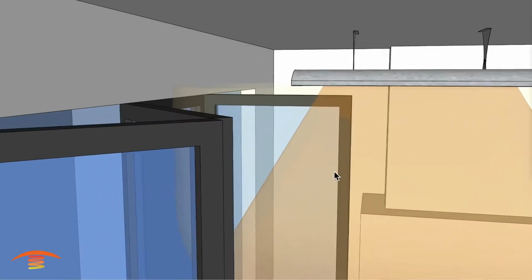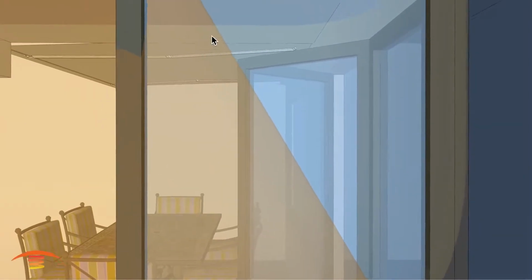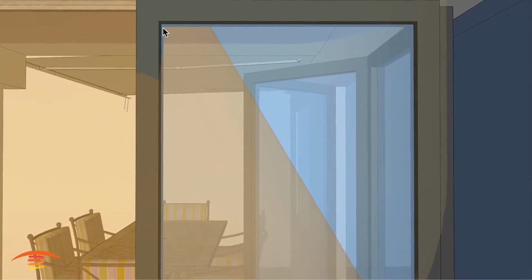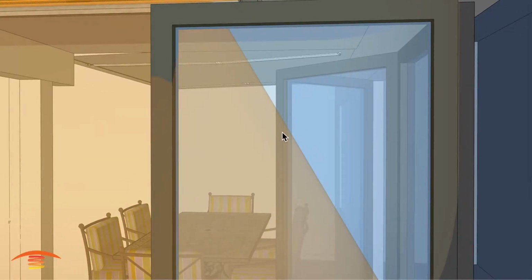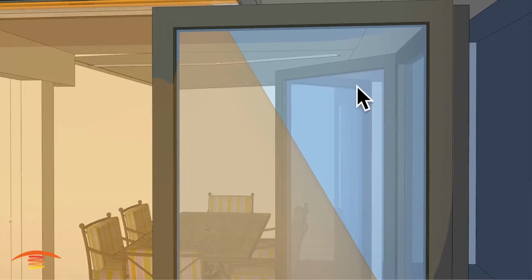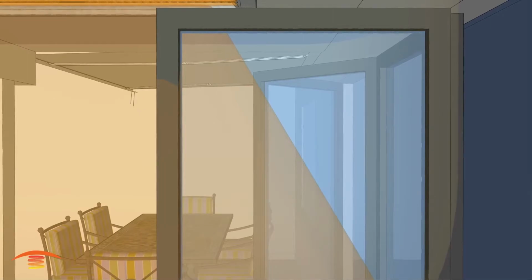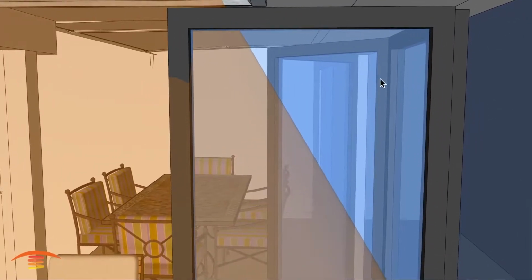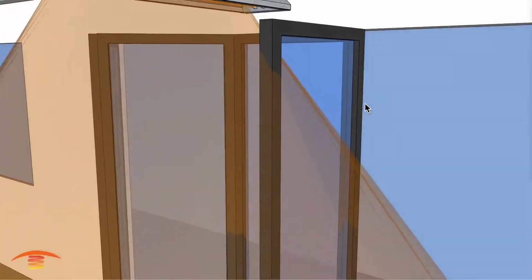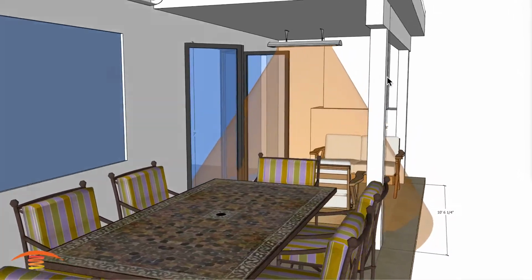However, you can see that we're meeting the clearance on this right side over here. But what you definitely don't want to do is have this heater on and then that ray penetrate the glass. It's a cold night, let's say, and so from this point here downwards, you have the penetration of the infrared light wave, but over here the glass is going to be the same as the ambient temperature outside, so it will not expand and contract evenly, and this will superheat down here, and this might crack over here. So that may not be a good option at all for this application.